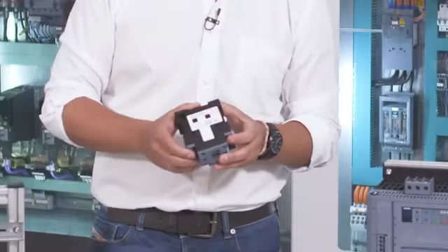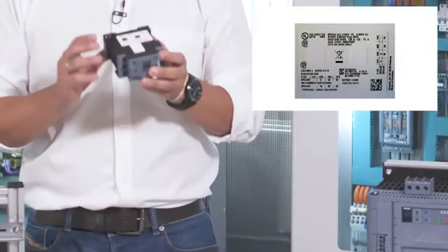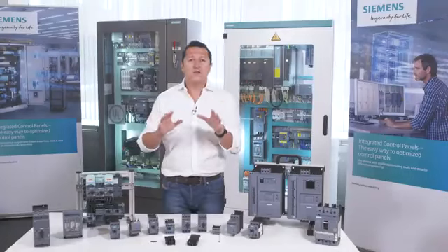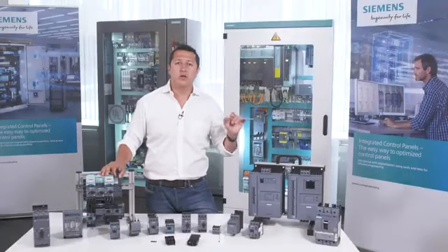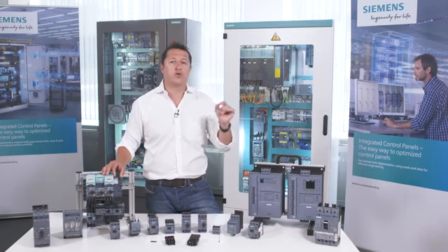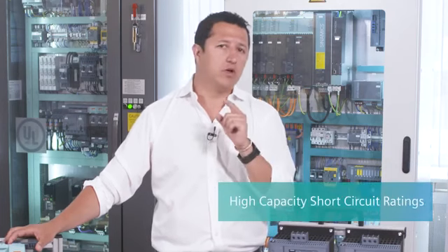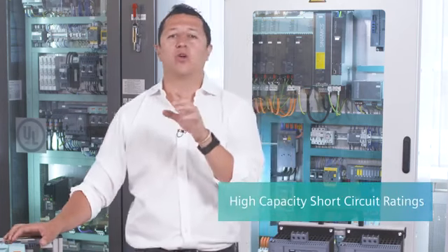The issue here is that for branch components, the standard SCCR is relatively low. As you can see here, the standard SCCR value is only 5 kA for a contactor up to 50 horsepower or 37 kilowatts, and for terminal blocks, even 10 kA. These values are often too little, in particular in industrial markets, to be the overall short-circuit current rating of the control panel. The most interesting, easiest, and practical method to increase the overall SCCR values or ratings of an industrial control panel is to use the high-capacity short-circuit current ratings based on tested combinations.